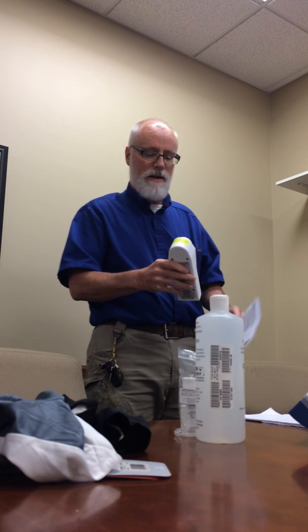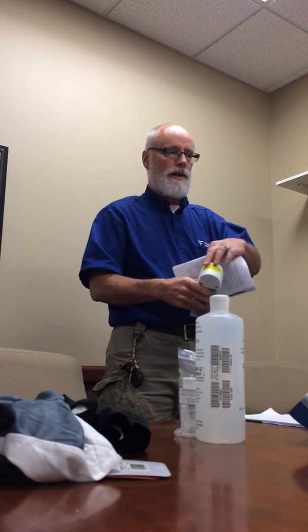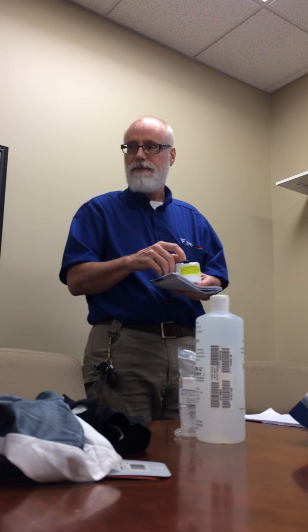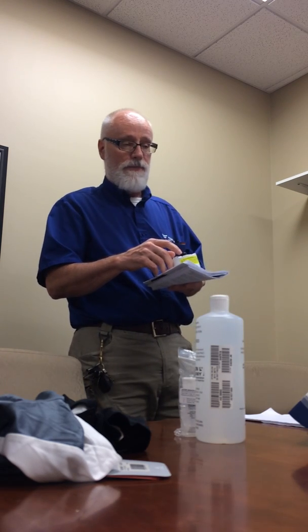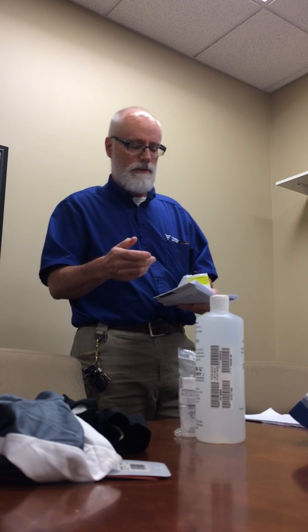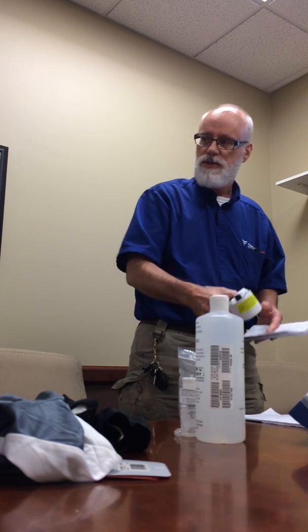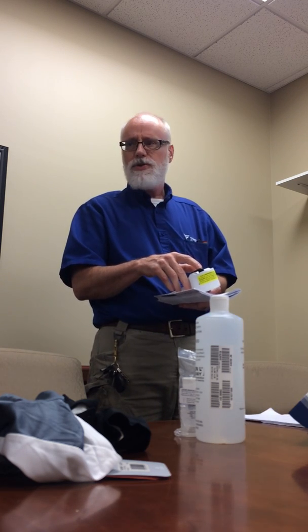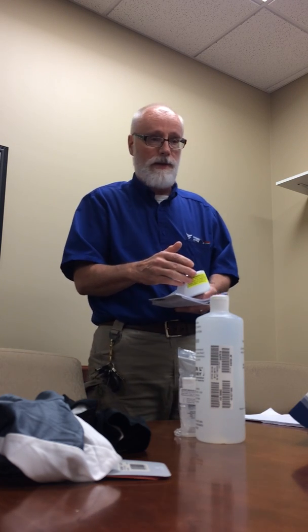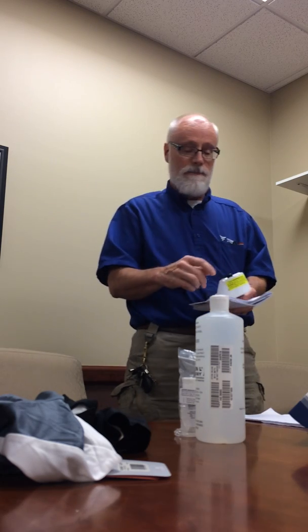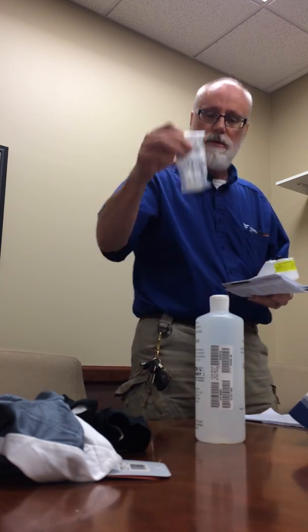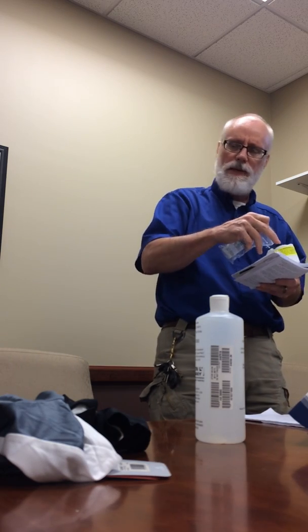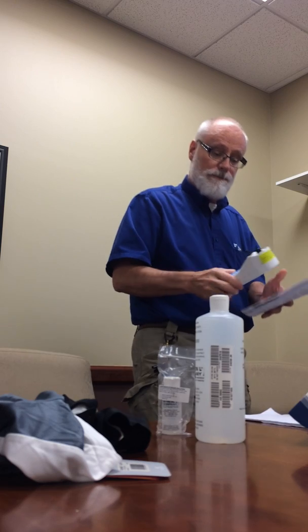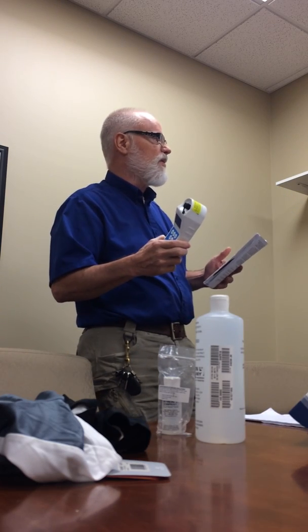I've been putting a sticker on here to remind them that when they put this pH solution in after they've used it, if it's more than 30 minutes—since they check dialysate fluid on a few machines and then they're done and it'll sit somewhere—they need to put the pH solution in there after that particular use. They might use it 3 or 4 times during the day intermittently, so make sure at the end of the day the pH solution is filled to the top and the cap is on. That's pretty much it as far as the introductory things.